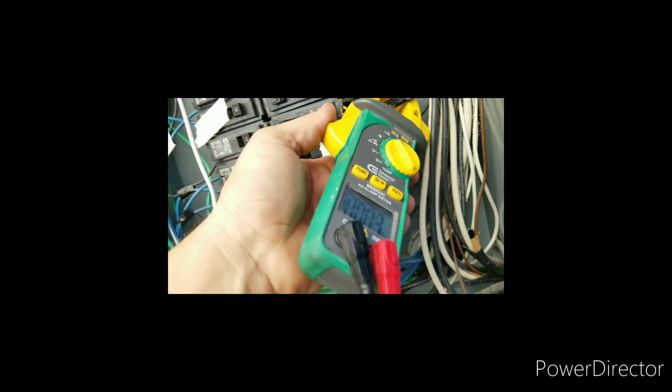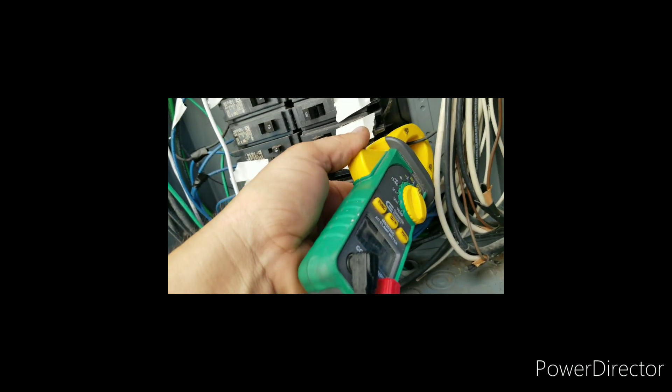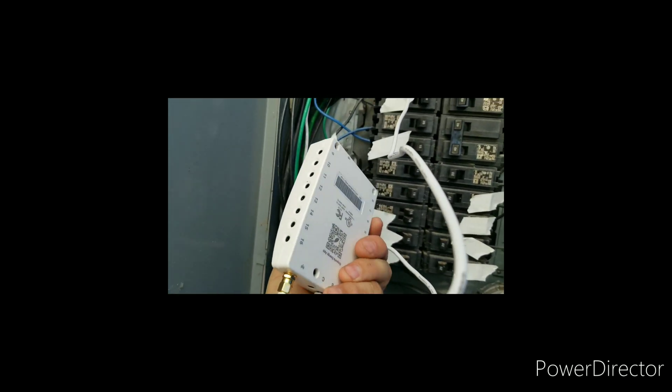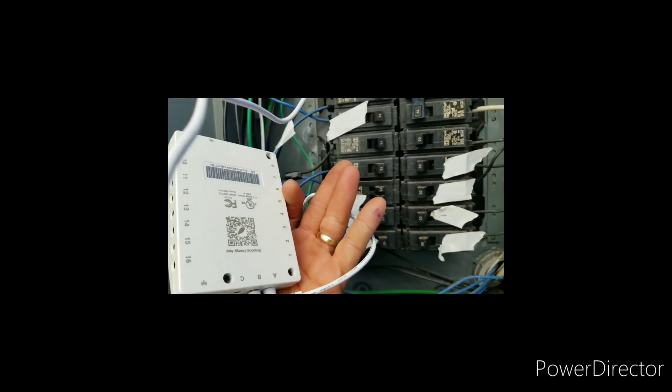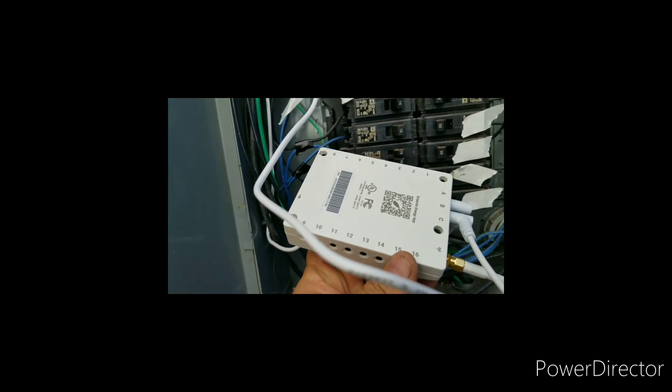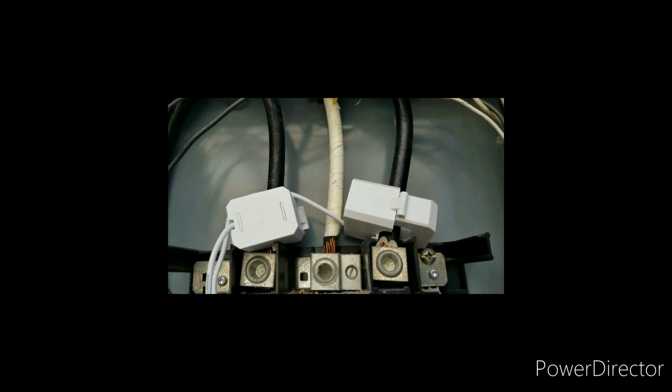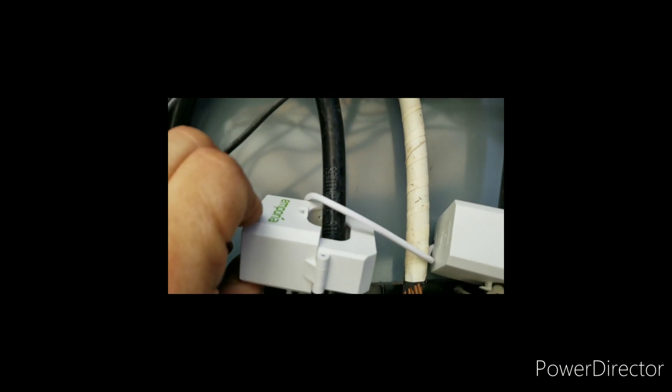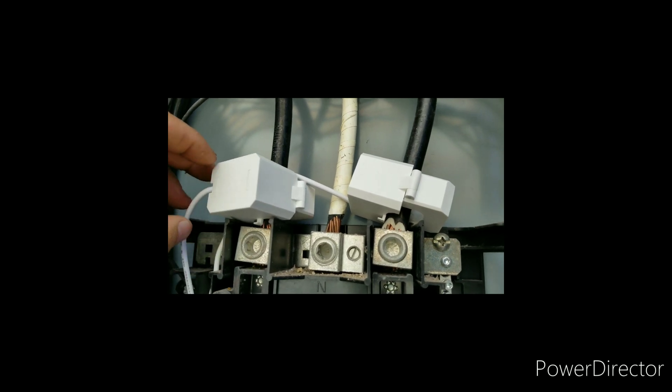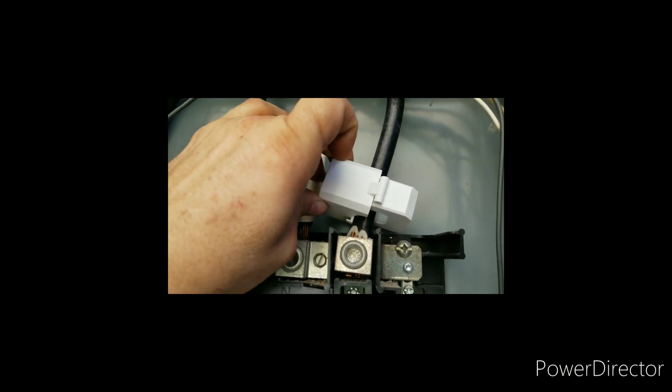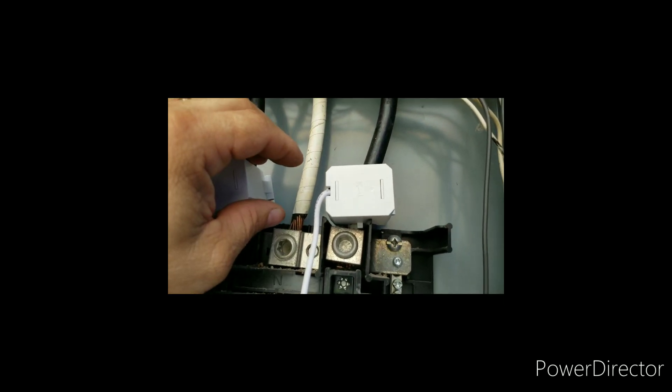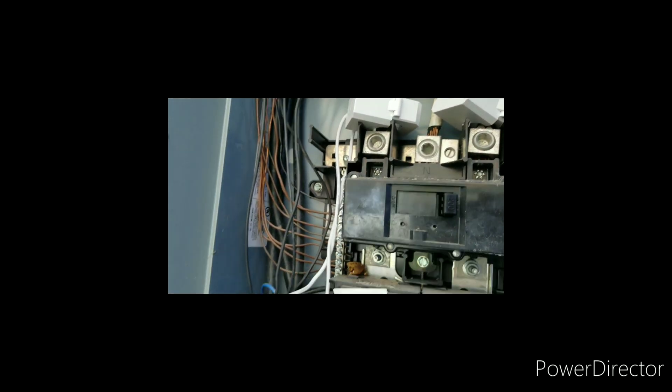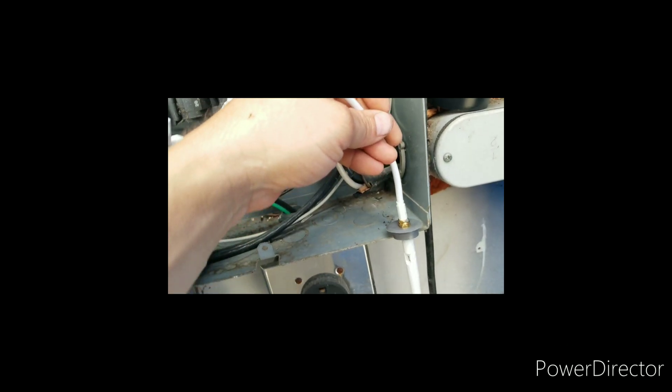Alright, so once I get all these ammeters on, I'll be able to plug them into their device. The device has 8 microphone jacks more or less on the back side. On this side has 8. On this side has 8 for 16. And on the top has A, B, and C for your phases. So I got phase A and phase B. It says to put the logo going towards the meter base. So it also shows K and L. Couldn't really find any literature in there, but it seems like it's asking for which way the load is going. So that is that. These guys just get tucked up in here. It'll end up going down into here. This thing has an antenna that can go through one of the knockout punches. So I'll get a knockout over here knocked out and then it'll have an antenna hanging out at the bottom. So once I get this thing filled up, I'll take another video.